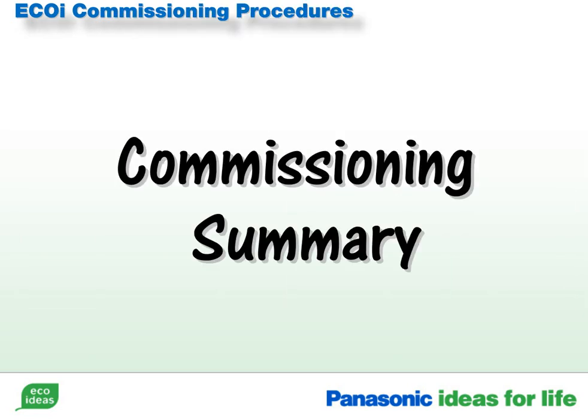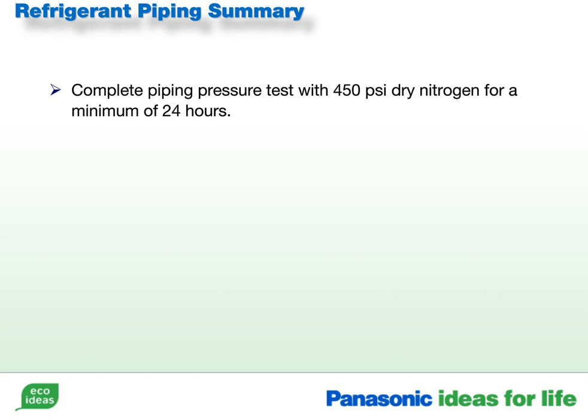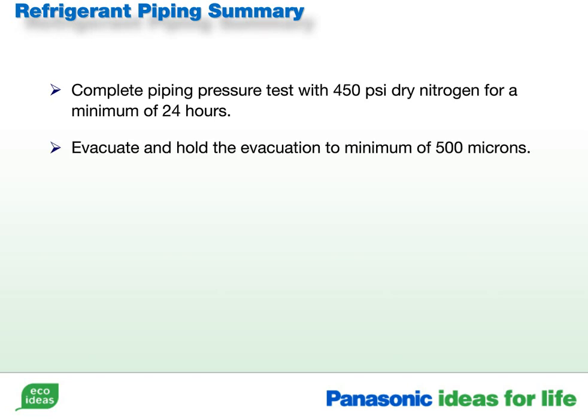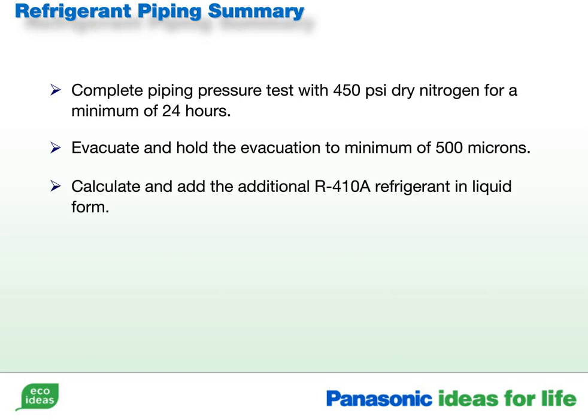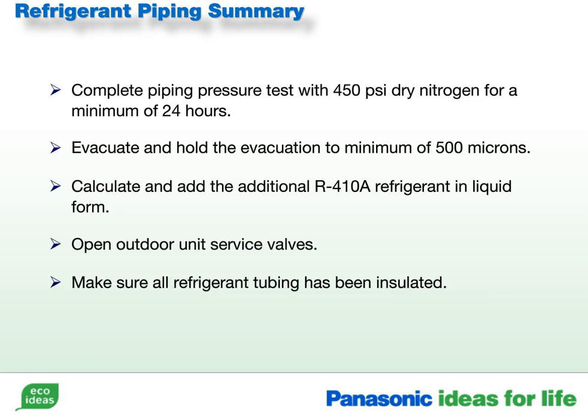Let's review the startup procedures. Summary for the refrigerant piping. Complete the third stage of the pressure test, with 450 psi of dry nitrogen, for a minimum of 24 hours. Evacuate the system to a minimum of 500 microns, and hold the vacuum for a minimum of 24 hours. Calculate and add the additional R410A refrigerant needed. Remember to always charge R410A in liquid form only. Open the outdoor unit service valves. Confirm that all of the refrigerant lines have been properly insulated.